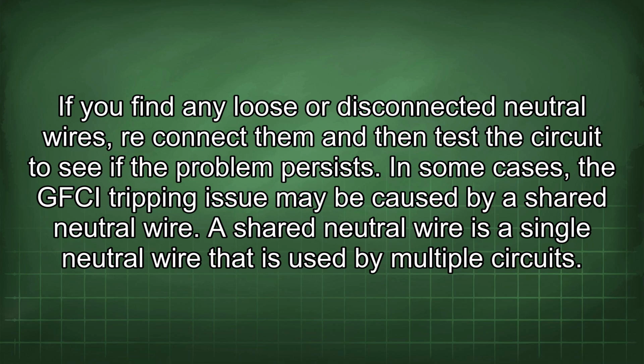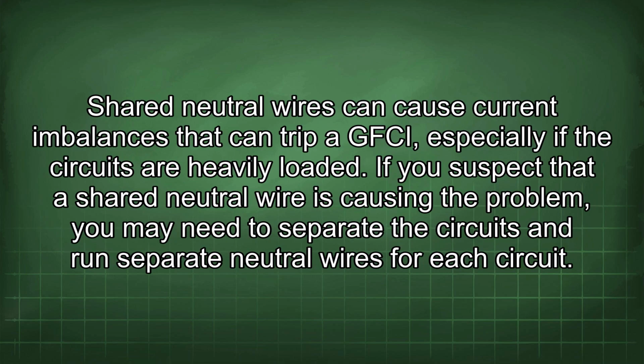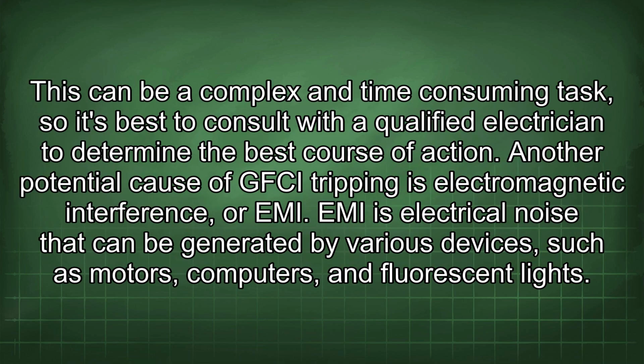In some cases, the GFCI tripping issue may be caused by a shared neutral wire. A shared neutral wire is a single neutral wire that is used by multiple circuits. Shared neutral wires can cause current imbalances that can trip a GFCI, especially if the circuits are heavily loaded. If you suspect that a shared neutral wire is causing the problem, you may need to separate the circuits and run separate neutral wires for each circuit.